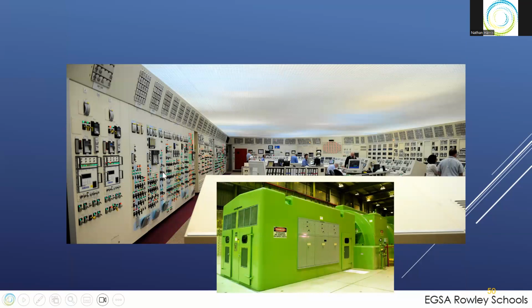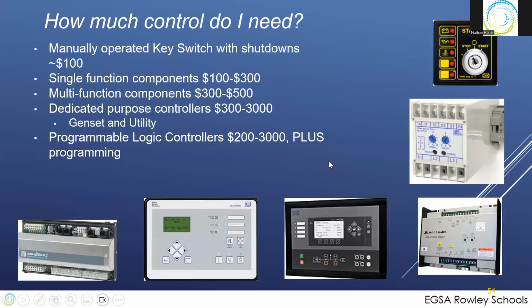So here are the electrical controls on the backside, protection and controls, the electrical distribution system, and here's all the mechanical stuff, and the boiler and turbine controls and all that are over here. So obviously the control system has to be much more than what we're normally used to dealing with. That just gives you kind of the spectrum of controls that are available. You can get just a key switch, like the top right picture. It's simply a key switch: stop, start, run. And it's got a couple of shutdowns. In that case, it's got a voltage and an oil shutdown, and looks like a temperature shutdown, and a couple more you can program with dip switches.